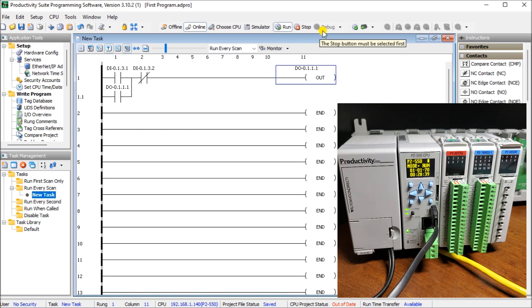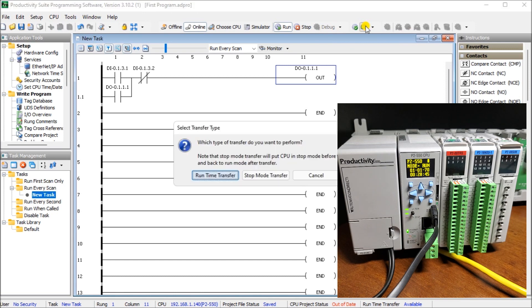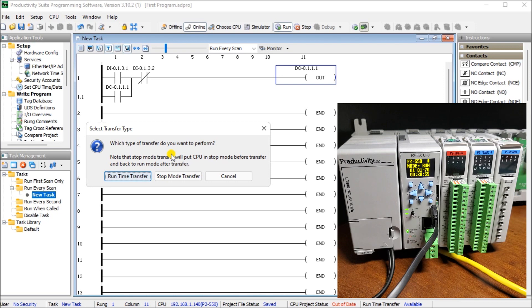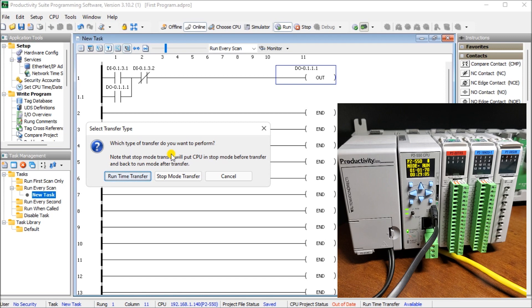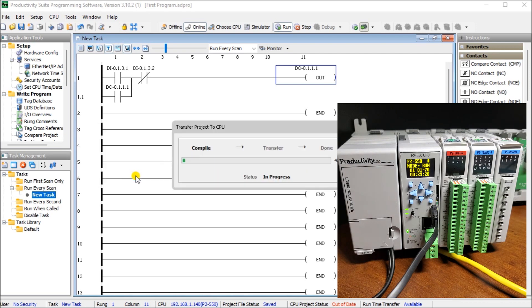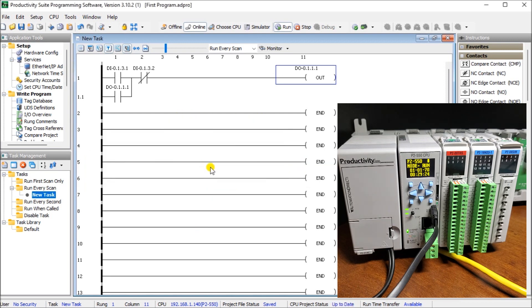So what we have to do now is just transfer this project to the CPU. And that's going to ask us, which type of transfer do you want to perform? Now, there are two types that we can have. We can have runtime transfer. That means that the CPU will not stop executing the logic and we hold the logic scan. We input our program and then allow it to continue operating. Or we go into stop mode, which the controller goes into stop. It stops executing both the program and then waits for us to put it back into run mode. We're going to do a runtime transfer in this case here. And that's it. Now you'll notice that our CPU project status is up to date.